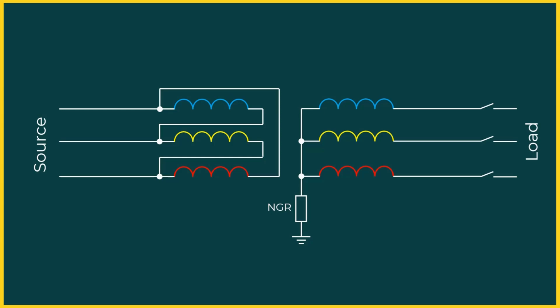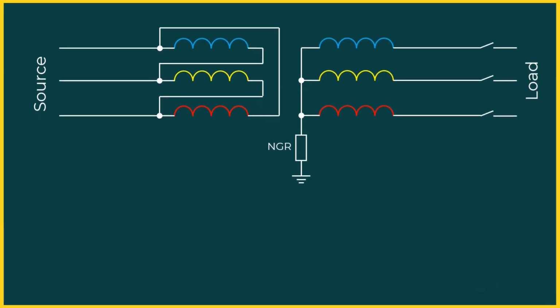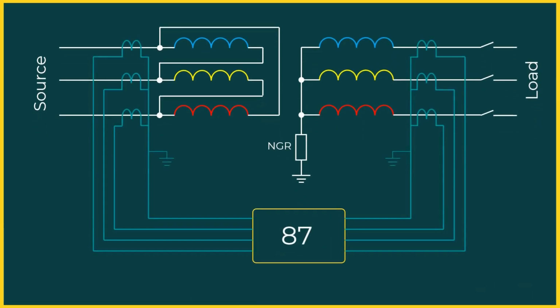Let me begin with a real incident from an electrical installation. A delta star transformer was in service with the star side neutral grounded through a low resistance grounding resistor, NGR. The transformer was equipped with the differential protection, the well-known 87 scheme. One day, a phase to earth fault developed in the low voltage star winding.